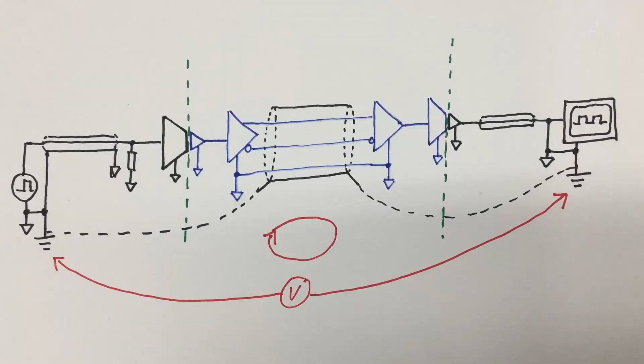However, if you look at this shielded twisted pair cable, used for Ethernet, you see the shield is connected to the metal parts around the plug, which make contact with the metal frame of the socket in the switch. You can expect it's exactly the same at the other end, going into a router or a PC or somewhere else. So the shield is connected here on both sides, and you obviously can get away with that.